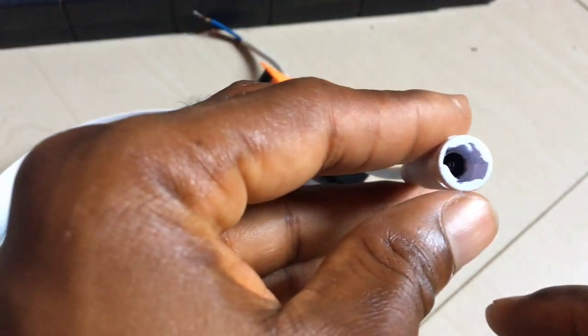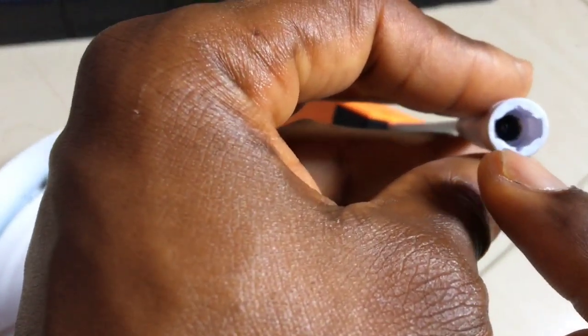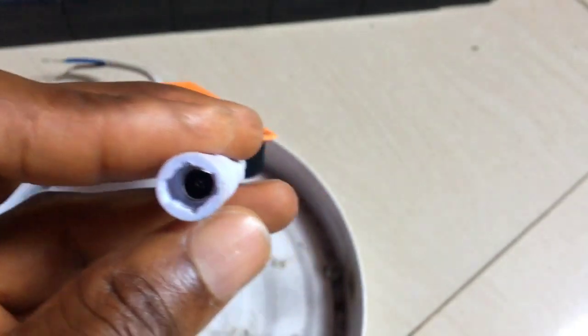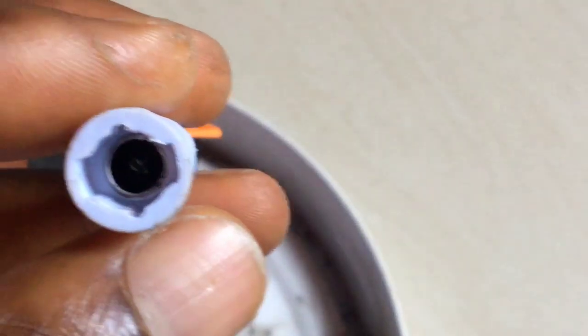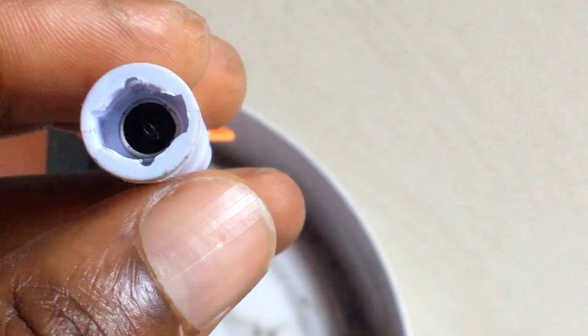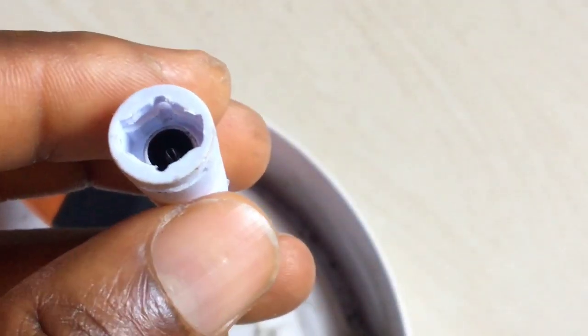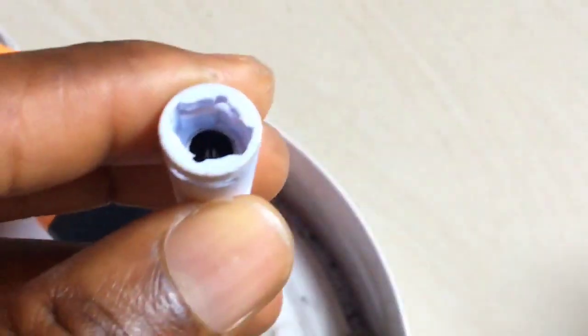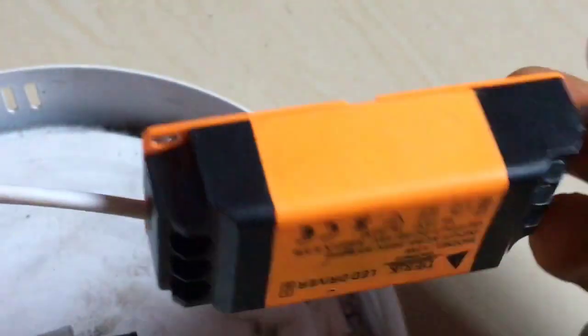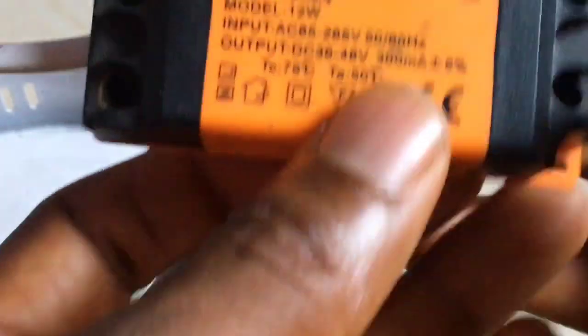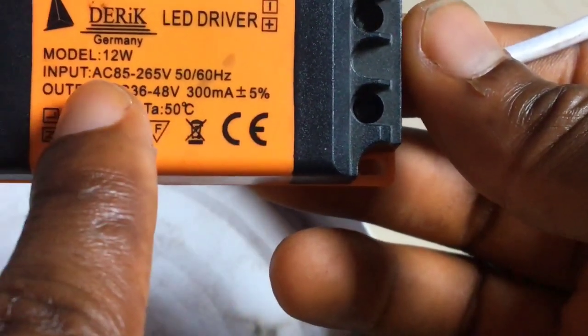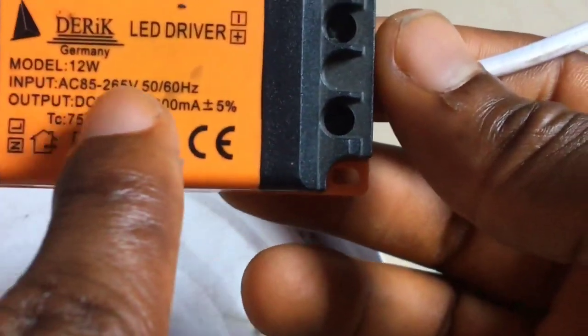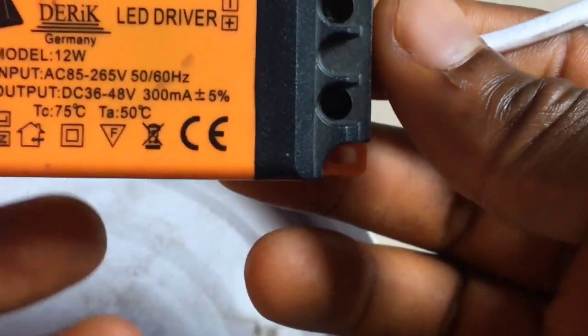If you have your multimeter, once you plug this terminal, if you test here, what you're going to get is DC voltage. You can see there is an inner terminal. I don't know how clearly we can see this. That inner terminal is where you place your red probe, and then there is an outer terminal, which is our black for the neutral probe. So that's how you test for voltage on a choke like this. You call it a choke or a driver, but it's actually a rectifier. You can see it's rated 12 watts, input AC 85 to 265 volts, and output it can deliver, it says, 36 to 48 volts DC.